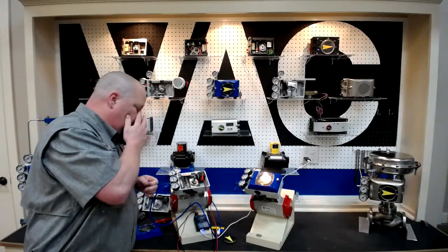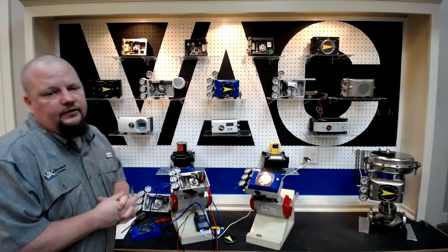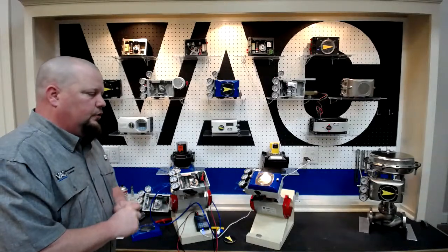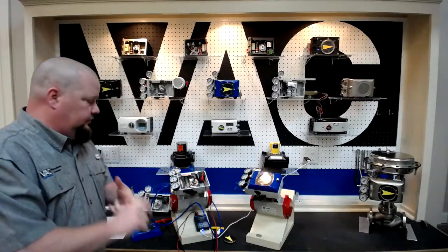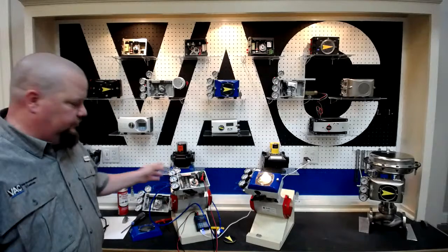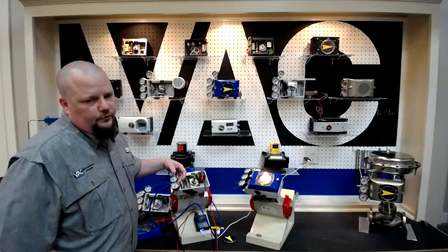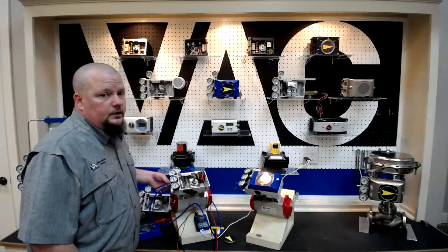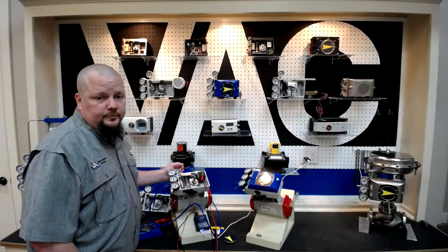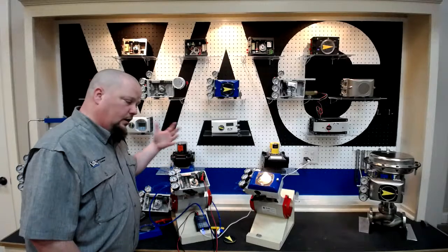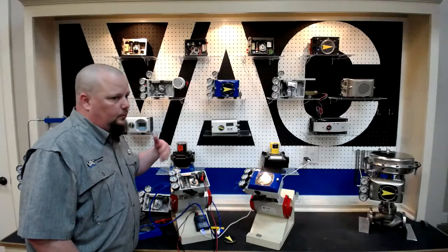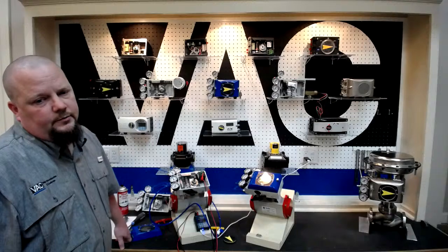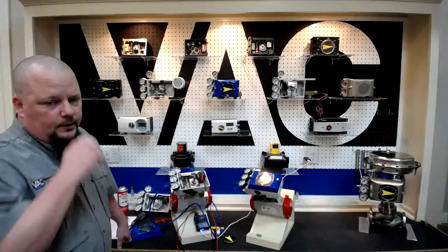Going back to operating, looking at a valve. So that's mainly the setup issues. Generally, the biggest things to watch out for are cam setup and the tubing, making sure the tubing is oriented properly, that you don't have the tubing reversed and that it's going for the particular operation you're looking for. There's a whole bunch of different ways you can set it up, and we talk people through those quite often, whether they want increasing signal to open or close, and making sure that the fail open or fail close valve works properly. It's things we do quite often on the phone.